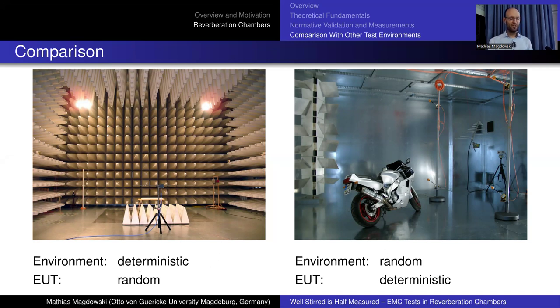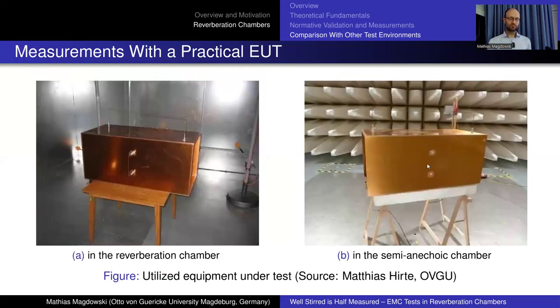The good thing is, here, this randomness, you don't know and you cannot control. And here you know it and you can control it because it's independent of frequency. It just depends on your number of frequencies. So this is the huge advantage on this side, let's say. So at high frequencies, I would strongly recommend doing emission measurements in reverb chambers because it's much, much, much more robust.